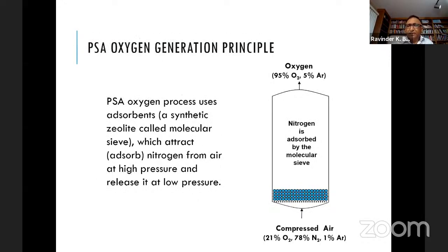So the way a system would work is that we use a vessel, which we call an adsorbent bed, fill it with the sieve, and pass compressed air through it. As the air goes through, the nitrogen is adsorbed. What comes out is oxygen and argon. There is 1% argon in the air, but by the time it gets through, it is comparatively 1 to 5 relative to oxygen. Oxygen is getting concentrated 5 times, and so does the argon.